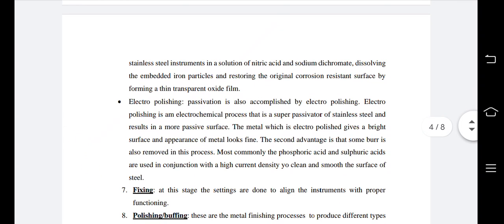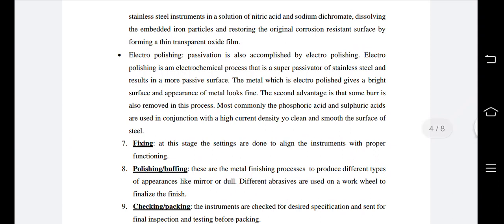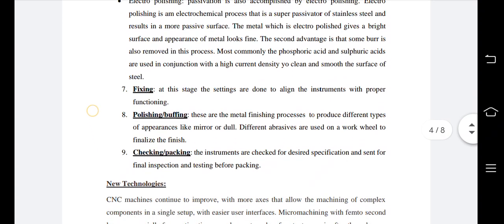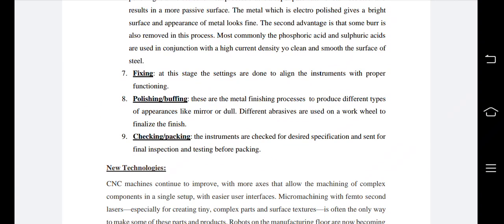Number 3 is electropolishing. Passivation is also accomplished by electropolishing. Electropolishing is an electrochemical process that is a super passivator of stainless steel and results in a more passive surface. The metal which is electropolished gives a bright surface and the metal looks fine. The second advantage is that some burr is also removed in this process. Most commonly, phosphoric acid and sulfuric acid are used in conjunction with a high current density to clean and smooth the surface of steel.